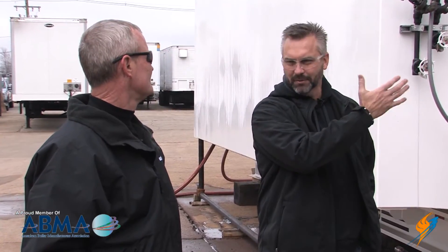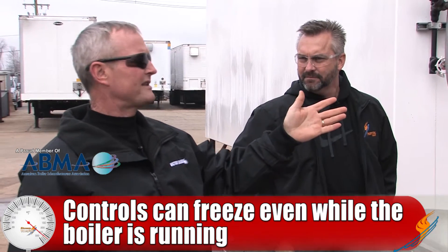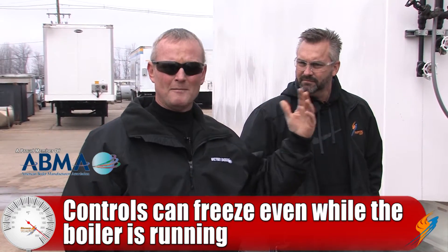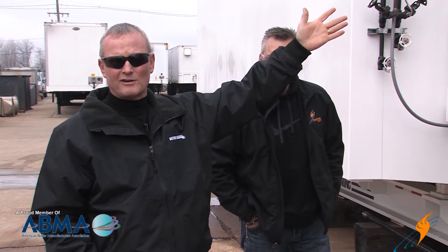The controls and everything — the boiler is running and all of a sudden the control lines could just freeze. They'll freeze up and give a false signal to the boiler, stating that it's either satisfied its pressure. If they freeze up and build pressure in that control, it'll satisfy it and shut the boiler down. Or it'll say that it hasn't been satisfied when actually the boiler pressure continues to rise, and the pressure switch doesn't verify that, so the boiler will continue to run until you pop a relief valve. You've got to keep those thawed out.